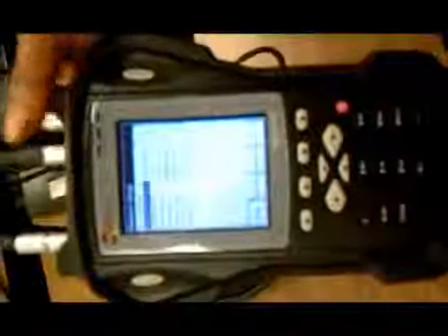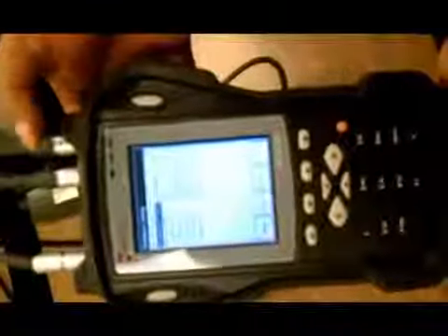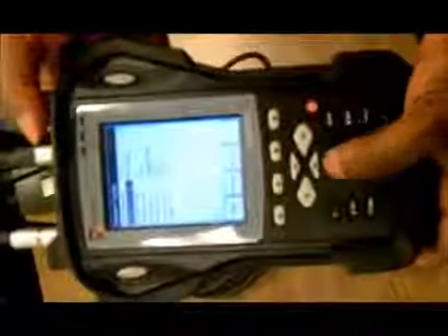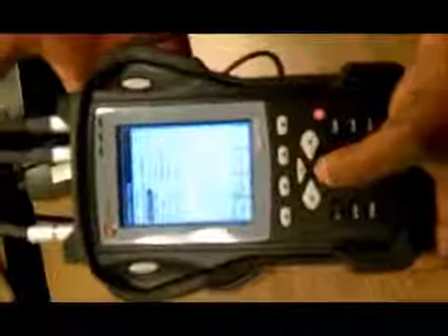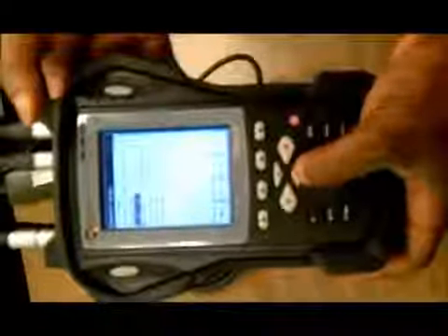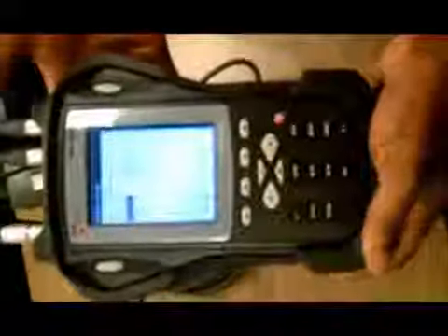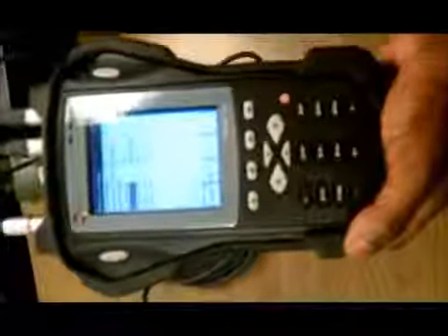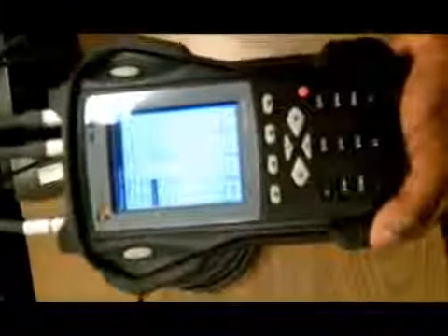And we're going to once again use the A to D mils because we have accelerometers and we want to change the readings to displacement. Our units in this case, we're going to use grams and inches as our length units. We have the option of how we want to count our angles. We're going to use against rotation. This means since it's rotating towards the wall, we're going to count the angle towards us.